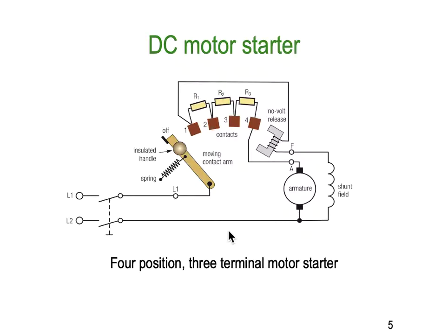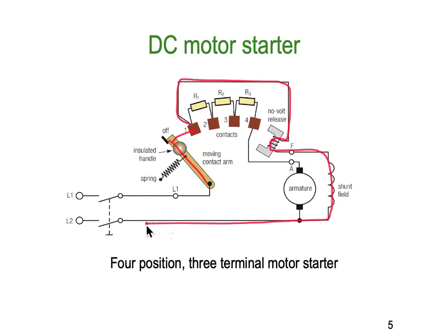DC motor starters. This is a 4-position, 3-terminal motor starter. Basically, you have a lever arm connecting the supply to the armature. When we move the arm across to the first position, we're going to have current through this release catch gadget into the shunt field and back to the supply. We're also going to have current feeding to the armature, but look how many resistors it has to loop through — all three of these resistors. These are reasonably large wattage resistors, and we're simply dropping the voltage to the armature so we have less starting current.